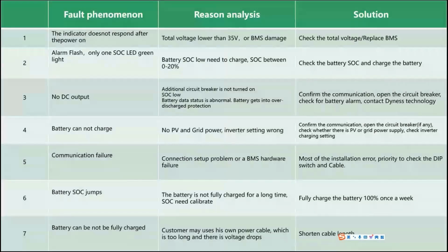And if all the settings are correct and it's just the BMS, a hardware issue, in this case you can get the BMS replaced. And there also, if the customer reports the battery SOC jumps, and maybe the battery was not fully charged for a long time, in these cases we need to charge the battery to 100% to have a test. When the battery is not fully charged for a long time, the SOC needs calibration, and only when fully charged to 100% will the SOC be accurate.